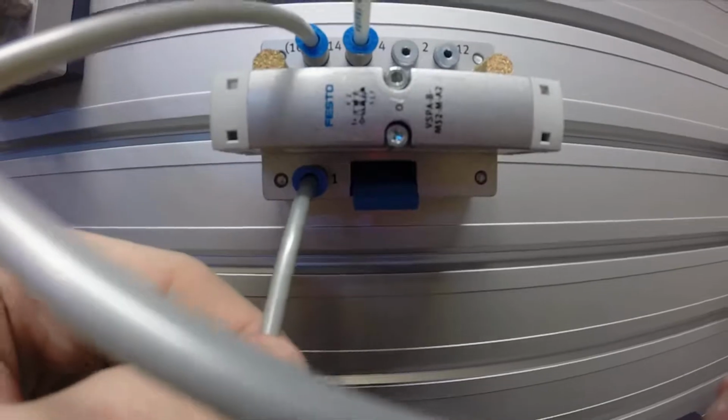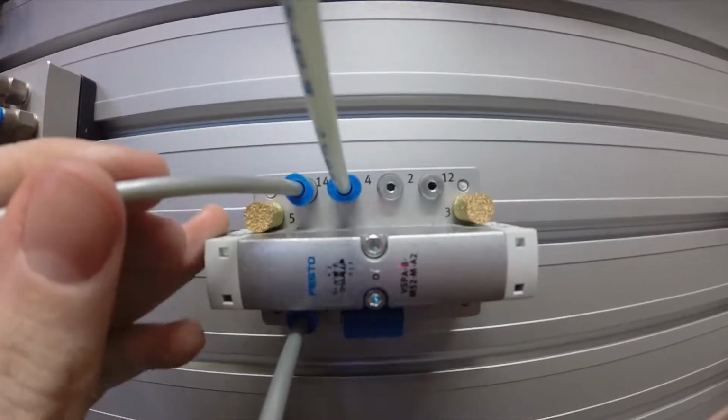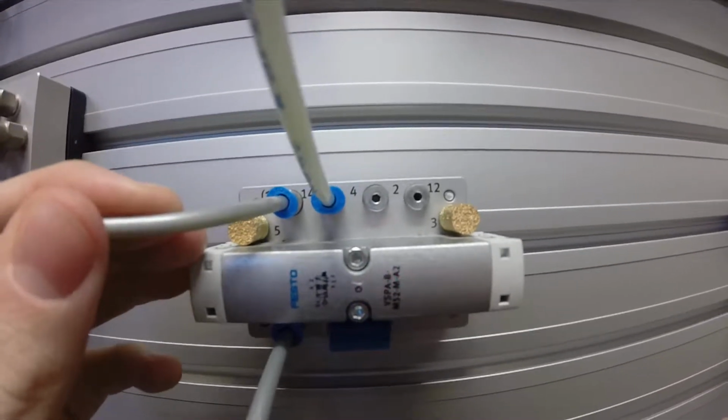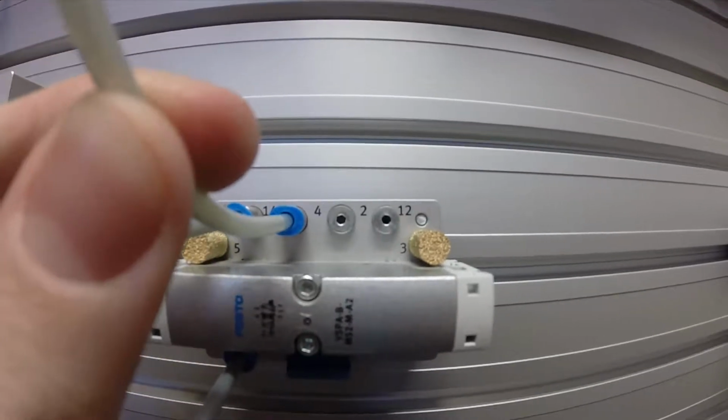You'll see that triangle, and that means it's pneumatically operated by a pilot line, which is like a pulse of air coming from another valve, and we see on the left it's got spring return. I suppose you can also say we've got our same sort of ports here. Then we've port 1 in there, and then we have port 14 up here, and port 4, which is our output port.